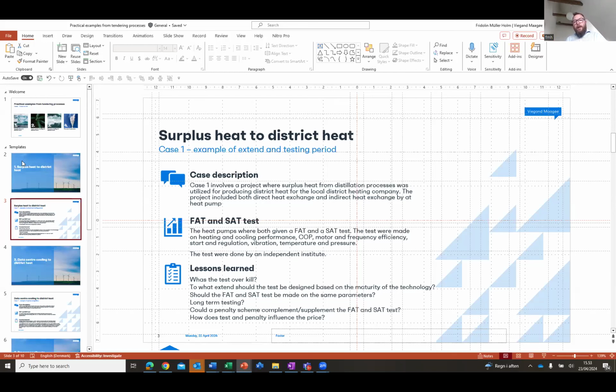Should we run the same test on both a SAT test and a FAT test, or should we differentiate more between the two? How do we deal with long-term testing? In this case we actually had a challenge with the heat pump afterwards — after a certain amount of hours of operation we faced some issues. This was not something we could discover during a FAT or SAT test.